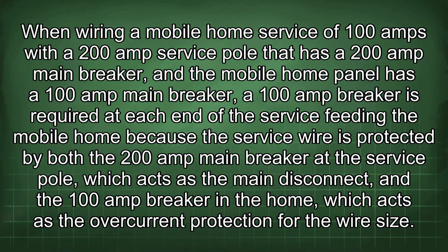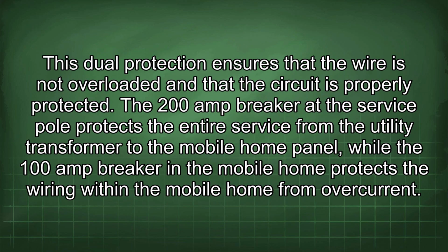When wiring a mobile home service of 100 amps with a 200 amp service pole that has a 200 amp main breaker, and the mobile home panel has a 100 amp main breaker, a 100 amp breaker is required at each end of the service feeding the mobile home because the service wire is protected by both the 200 amp main breaker, the service pole, which acts as the main disconnect, and the 100 amp breaker in the home, which acts as the overcurrent protection for the wire size. This dual protection ensures that the wire is not overloaded and that the circuit is properly protected.